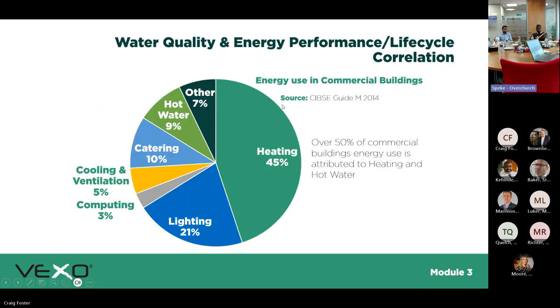This is why it's so important: 50% of the energy in a building is attributed to HVAC — your LTHW and hot water creation. When looking at reducing carbon emissions or operating costs, attacking the portion that generates the highest emissions is key. That can be achieved either through water quality — straining and cleaning new equipment — or via controls, such as at Somerset House, controlling plant more efficiently through weather compensation rather than time schedules, or on the secondary side creating individual control zones.